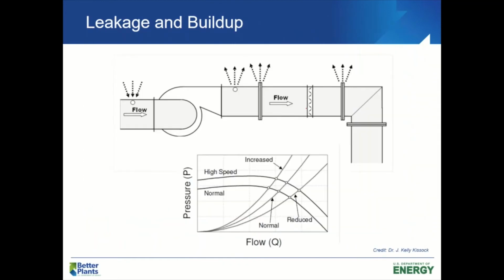All right, so another thing, and this is, again, big items, but it's part of that flow, okay, is really some of the leakage in our system and trying to make our ducting tight, okay? Most of us, you might have heard about something like this in your house or your home, right? Sealing ducts so you're not losing air. Within your homes, it's important because, well, you're paying a lot of energy to either heat or cool that air, but in addition, you're also paying extra energy in your fan to push air where it's not needed, okay?